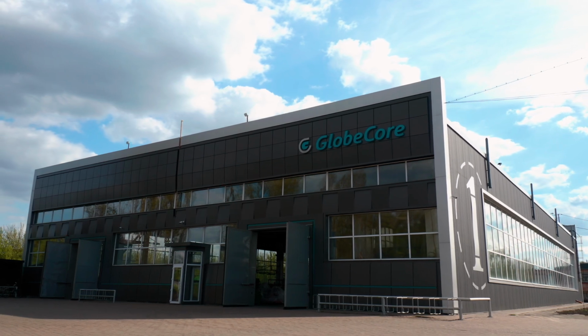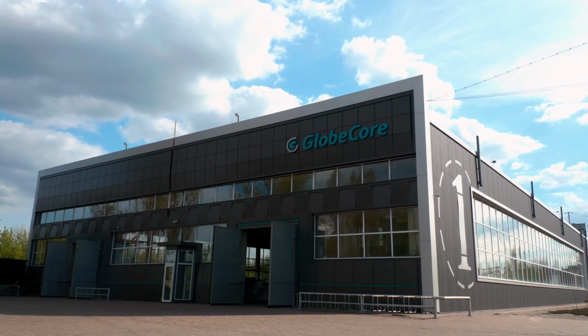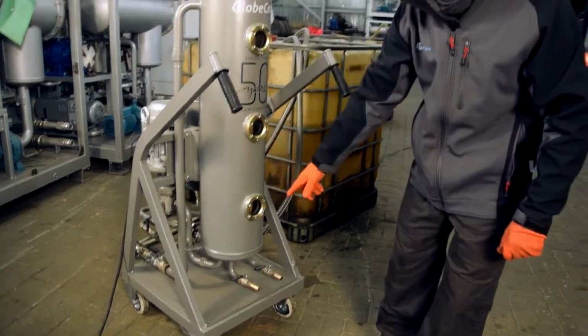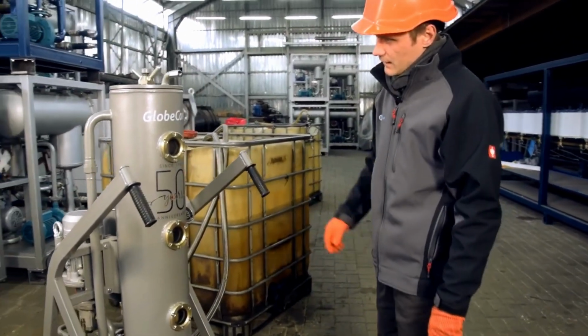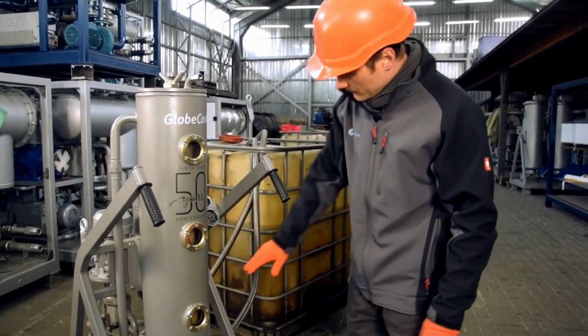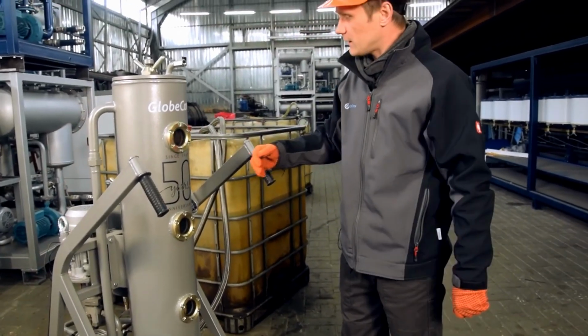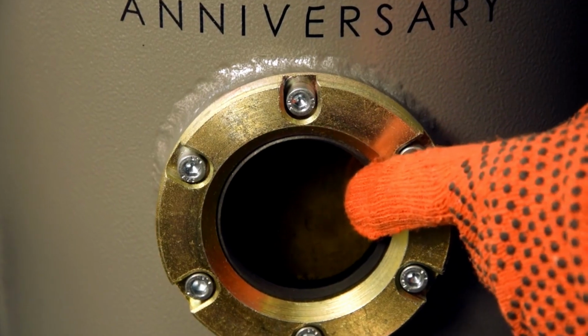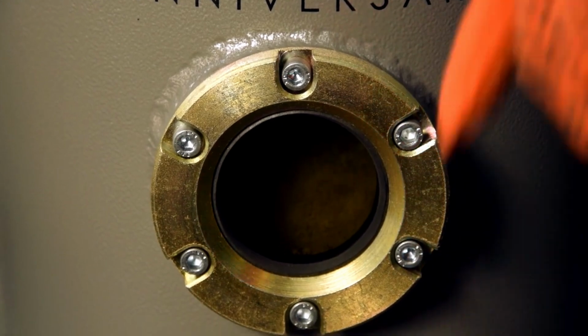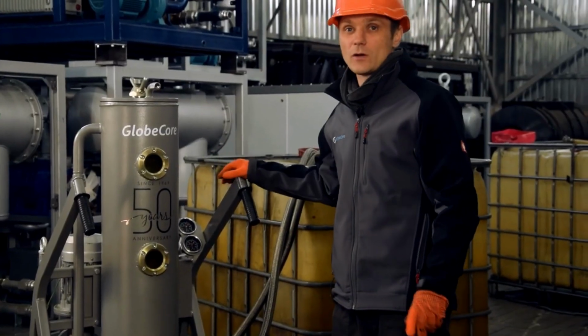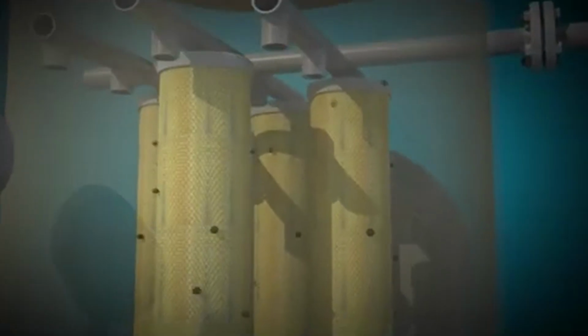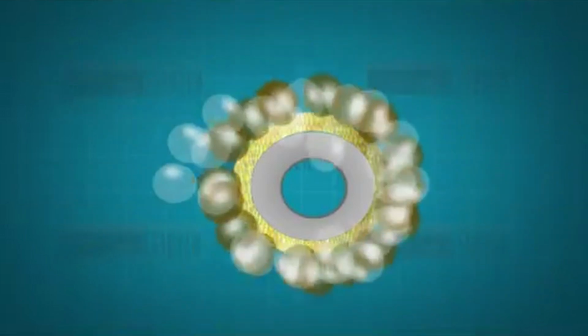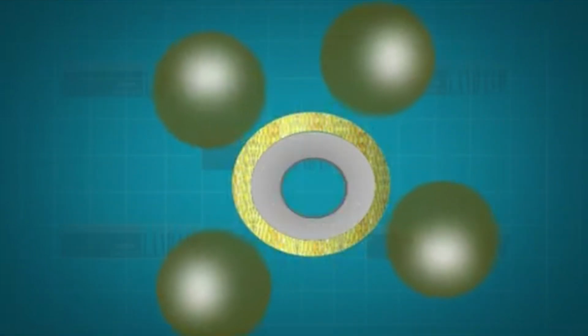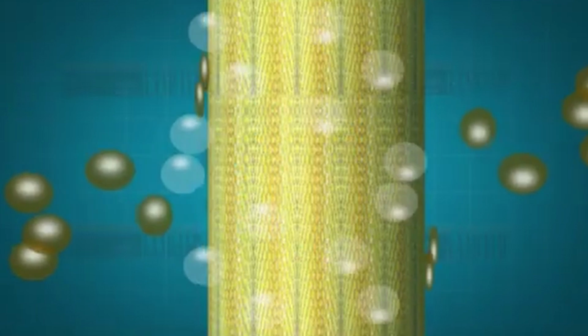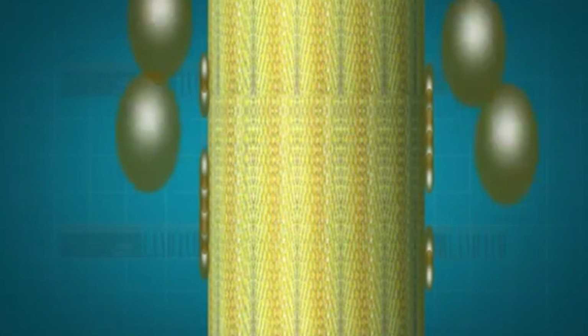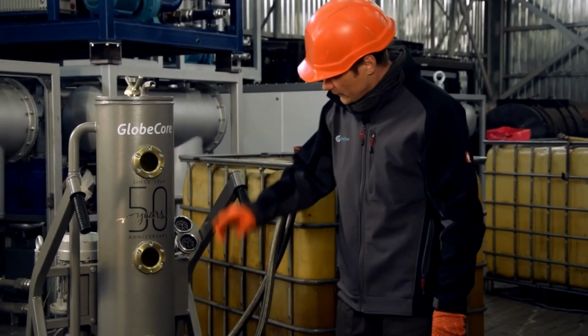GlobeCore has developed a technology for waste turbine oil regeneration which involves two-stage processing. At the first stage, particulate matter and water are removed from turbine oil using a CMM-1 machine. This machine removes solids through coarse and fine filters, and water through a coalescing filter. The use of a coalescing filter allows purifying even particularly water-cut oils with a water content of up to 50%, which is best suited for turbine oils.